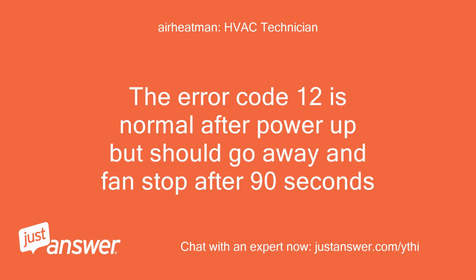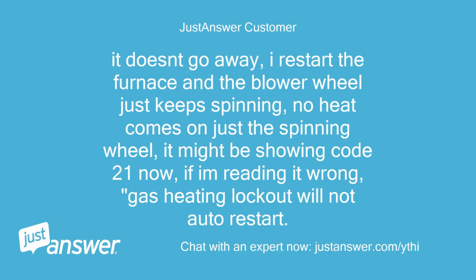The error code 12 is normal after power up but should go away and the fan stop after 90 seconds. It doesn't go away. I restart the furnace and the blower wheel just keeps spinning. No heat comes on, just the spinning wheel. It might be showing code 21 now. If I'm reading it wrong, gas heating lockout will not auto restart.